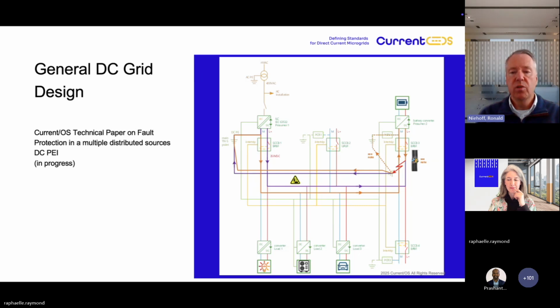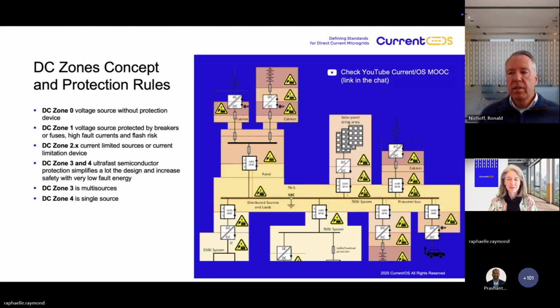And what we have seen already in the document is that with this architecture, isolated interlink converter, central TNS point with the system reference conductor next to the active front end, we can cover all the aspects related to safety for DC prosumer electrical installations. The next slide is about the DC zones concept.